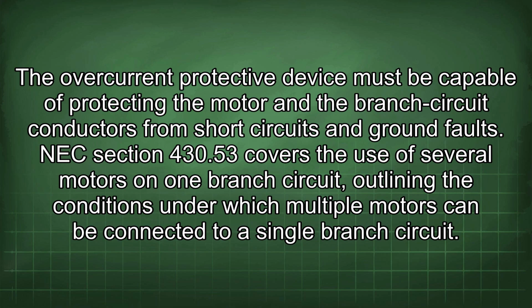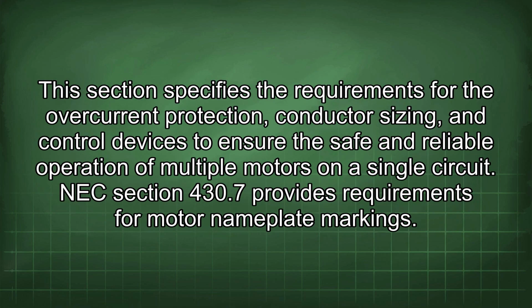ground faults. NEC Section 430.53 covers the use of several motors on one branch circuit, outlining the conditions under which multiple motors can be connected to a single branch circuit. This section specifies the requirements for the overcurrent protection, conductor sizing, and control devices to ensure the safe and reliable operation of multiple motors on a single circuit.